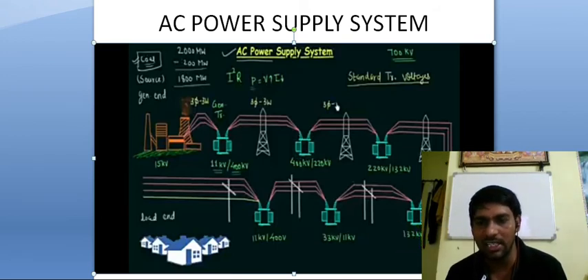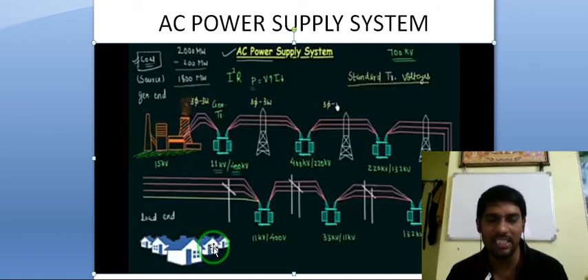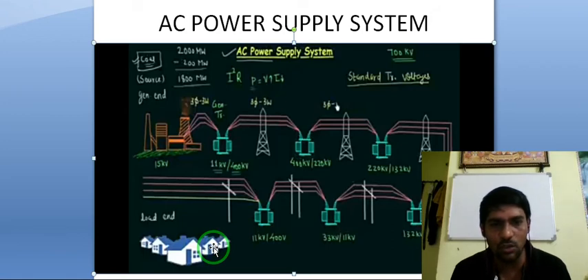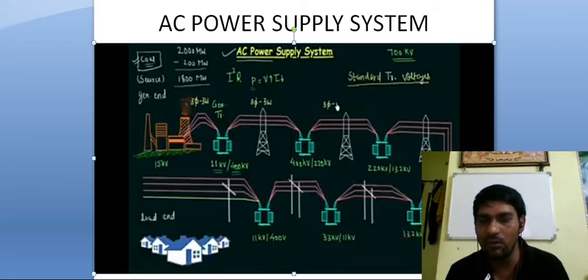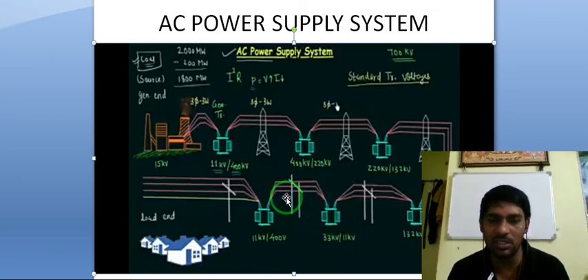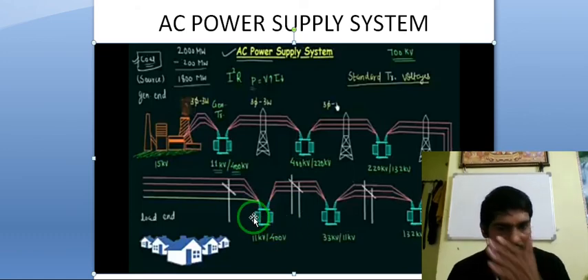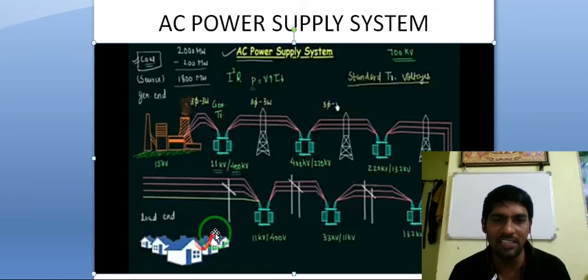Again, we cannot use this 33 kV directly for the loads, because our load required voltage is three phase 400 volts, and single phase 230 volts is more than enough, whether it is a single phase or a three phase. If it is single phase loads, we require 230 volts. If it is three phase loads, we require 400 volts. For that, again we step down the 33 kV to 11 kV. Again we transmit this 11 kV through the three phase line. Again we step down by this transformer, the 11 kV to 400 volts. So this 400 volts is utilized by the three phase consumers as well as single phase consumers.